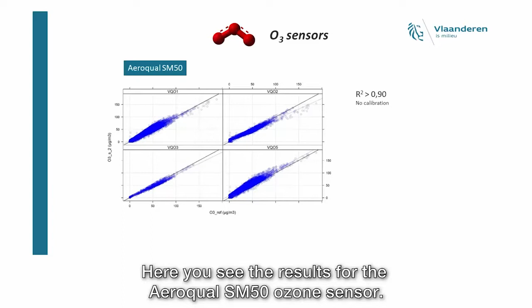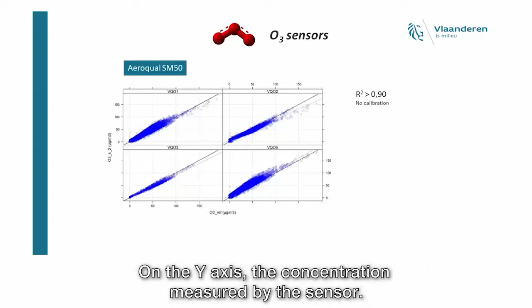One of the ozone sensor types, the Aeroqual SM50, performed very well straight out of the box, with an R-square of over 0.9. Here you see the results for the Aeroqual SM50 ozone sensor. On the x-axis is the ozone concentration measured in the reference station, and on the y-axis, the concentration measured by the sensor. We see that there's a very good correlation and an R-square of over 0.9. For this sensor, no calibration was necessary.